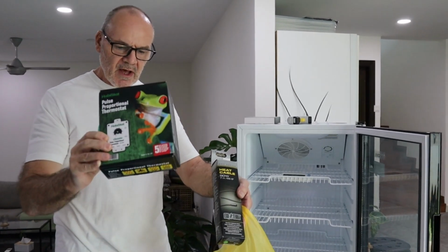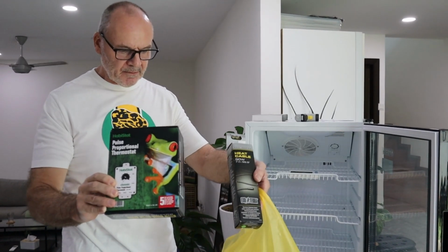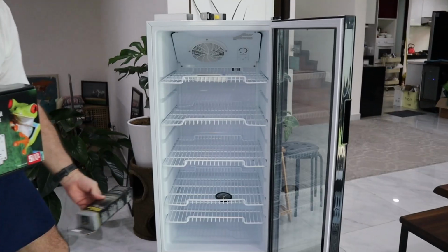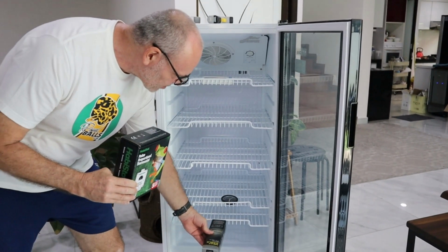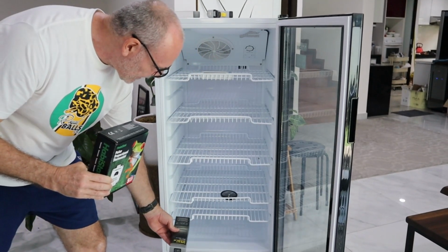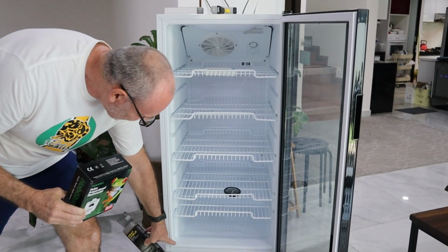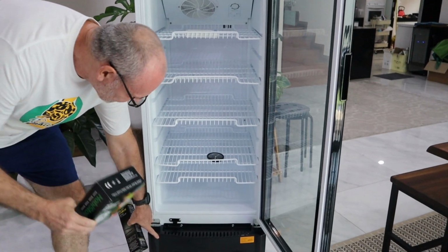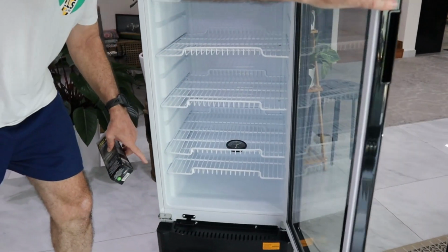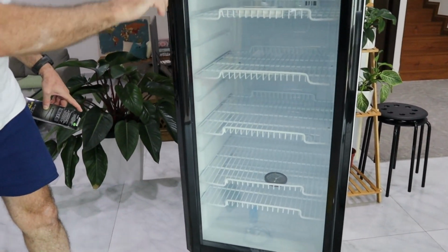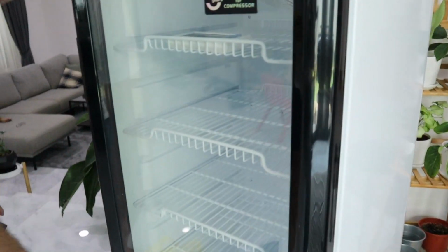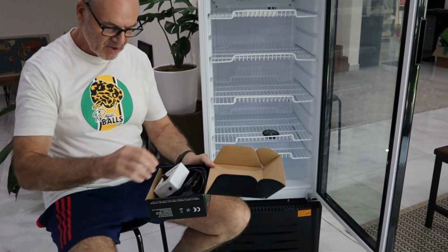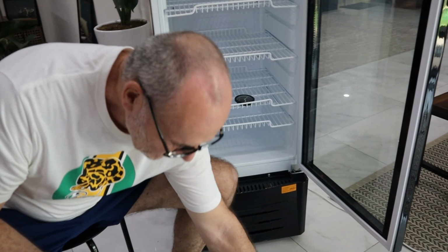So I'm going to use this pulse proportional thermostat with this heat cable. I'm going to attach heat cable to the bottom of the lowest tray in the incubator, and I can tape it to the side and out to the thermostat on the floor, and it will run through the door seal without having to modify the chiller in any way. I can run the cable. So let's take a look at the thermostat.